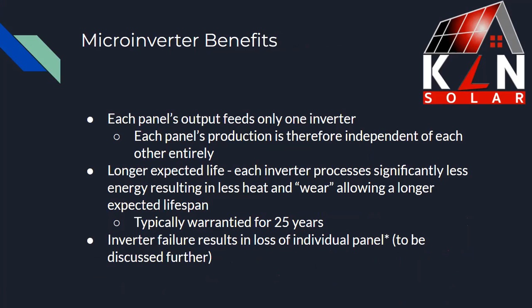What are the benefits of microinverters? With each panel's output, you're only feeding one inverter, so each panel's production is independent of each other entirely. There is no tying together when it comes to production. You have a longer expected life because each inverter is processing significantly less energy — only the energy from one panel. That results in less heat, less wear and tear, and a longer expected lifespan, usually warrantied for about 25 years. And if you do have inverter failure, it results in the loss of one individual panel rather than the whole system.